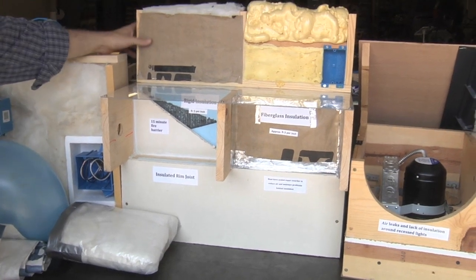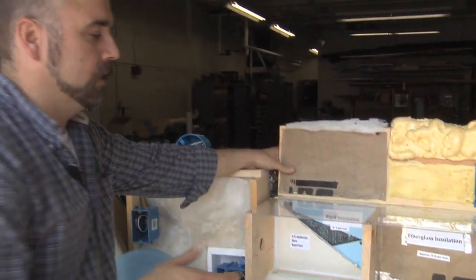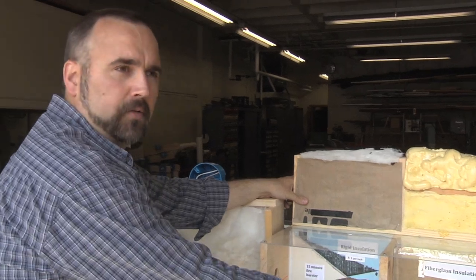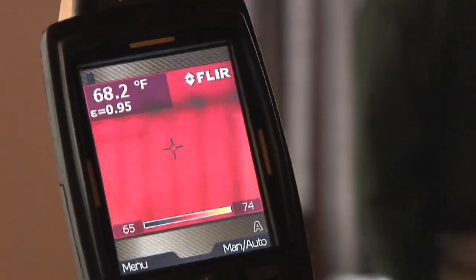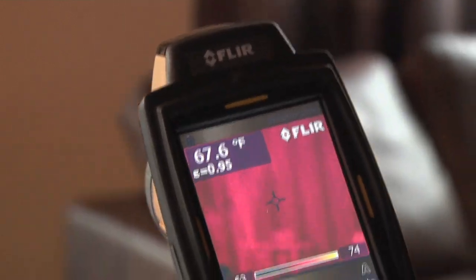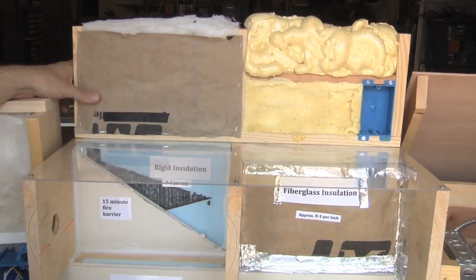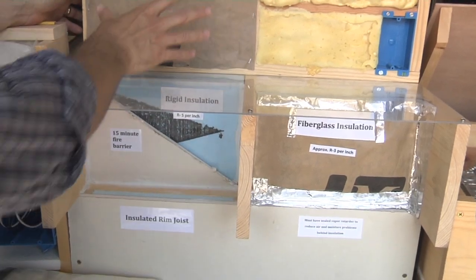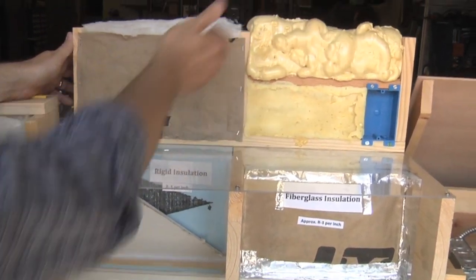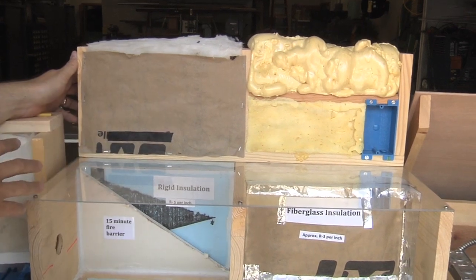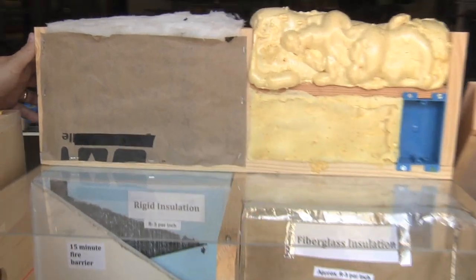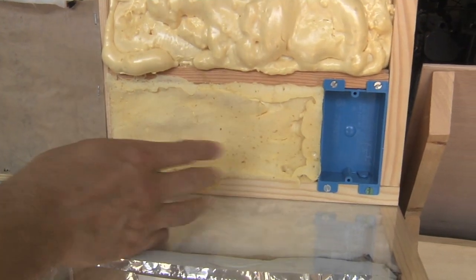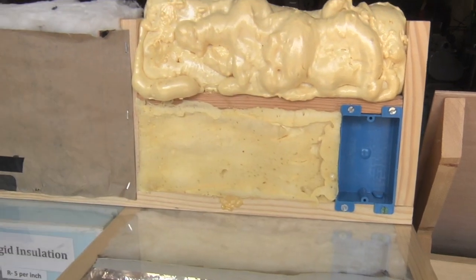Looking at our rim joists, we can see other examples of where heat can transfer out. With an infrared camera you can really see each one of these rim joists — every two-by-six or two-by-four in the wall cavity every 16 inches on center. For this two-by-four wall, we have an R13 value. Over here we have spray foam insulation, which has a higher insulation value and also air seals, getting behind those electrical boxes so we don't have that air transfer.